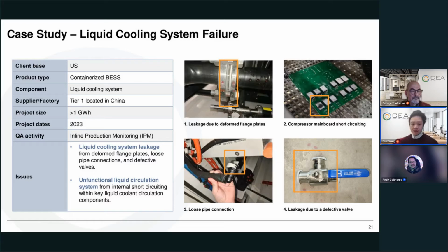Moving on to the next case study, we have a case study here on the liquid cooling system failure. The liquid cooling system really became necessary with increasing adoption of larger prismatic LFP cells. We're talking about 300 amp hour level and above cells. Liquid cooling is definitely a more efficient way of cooling compared with air cooling systems. However, this comes with increasing system complexity. Essentially, with the liquid cooling system, we are introducing an additional coolant circulation loop, and all the instrumentation and equipment that goes into it. And this, of course, introduces additional hazards, including coolant leakage.